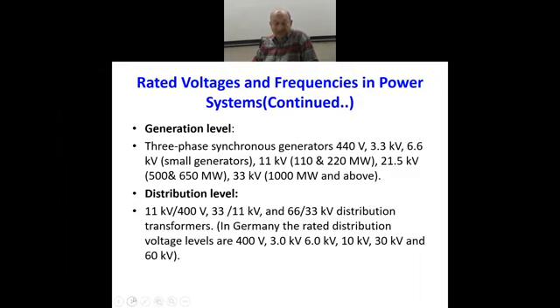Then, as I was mentioning, 11 kV to 440 volts, 33 kV to 11 kV and 66 kV to 33 kV are the steps at which the power distribution takes place. And ultimately, the consumption is either three phase 400 volts or single phase 230 volt. You would wonder why these are multiples of 11. That is why we have been calling it 440 volts and not necessarily 400 volts.